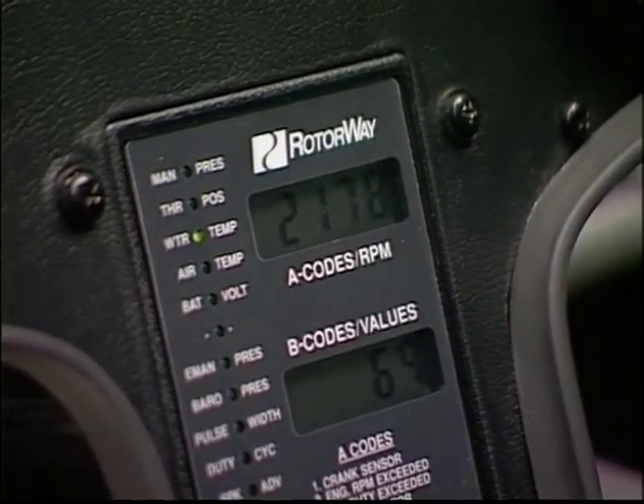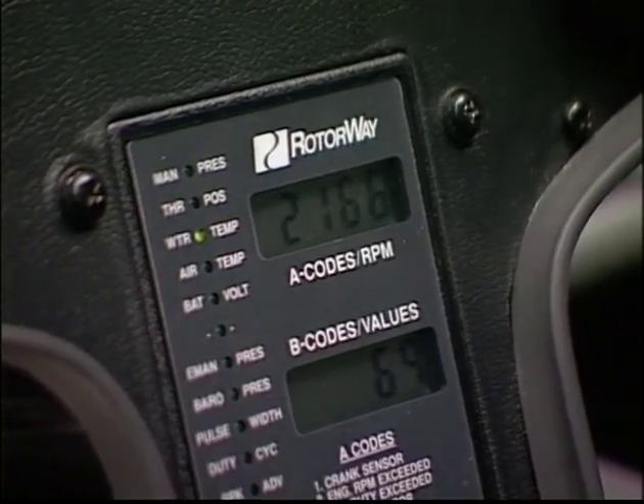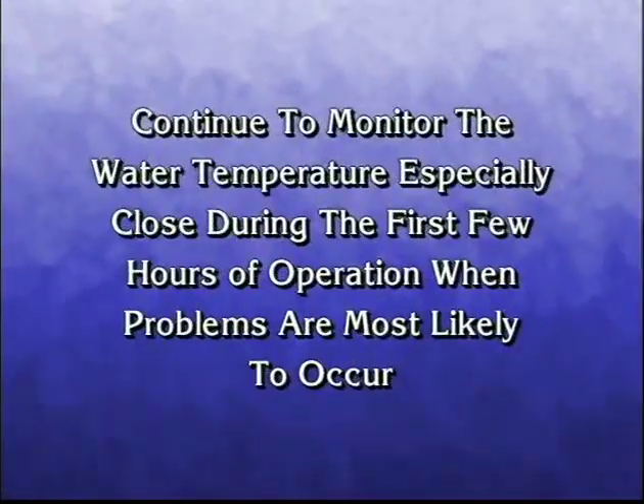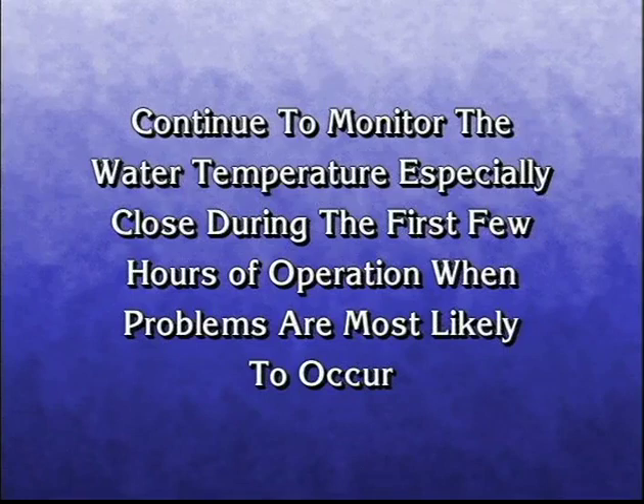Rebleed the system after each of the first few runs to ensure the complete removal of air. Continue to monitor the water temperature, especially closely during the first few hours of operation when problems are most likely to occur.